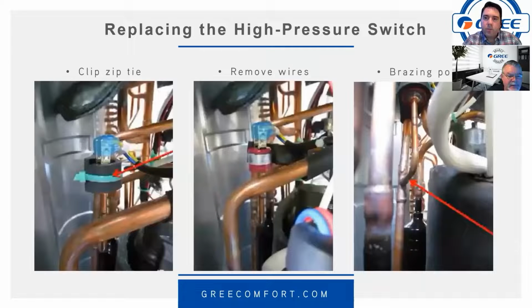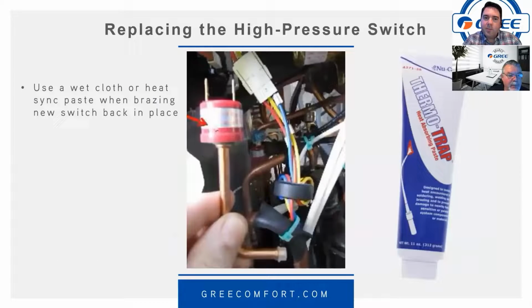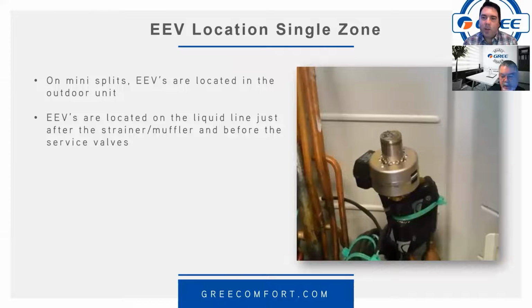And then to replace this switch, cut the zip tie off there, remove the insulation from around it, take the wires off, and now you've got to braze it in. So if you're going to replace one of these switches, please use some kind of thermo trap or some type of heat absorbing compound. A wet rag works fine, but make sure to protect that switch and anything else that's around it. We don't want to melt it while we're installing it, right? No, that could be problematic. You might get another E1. Of course, then it might be welded closed.